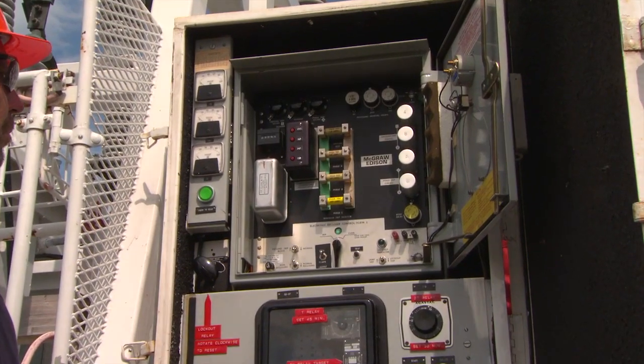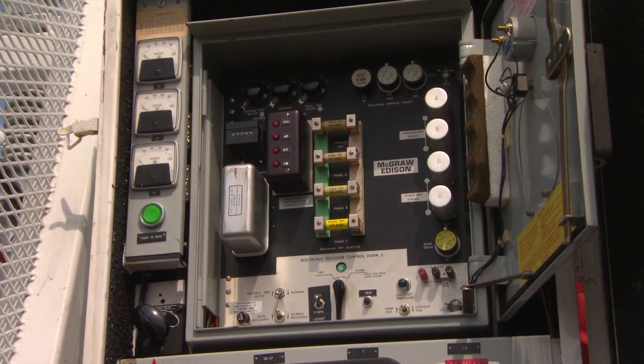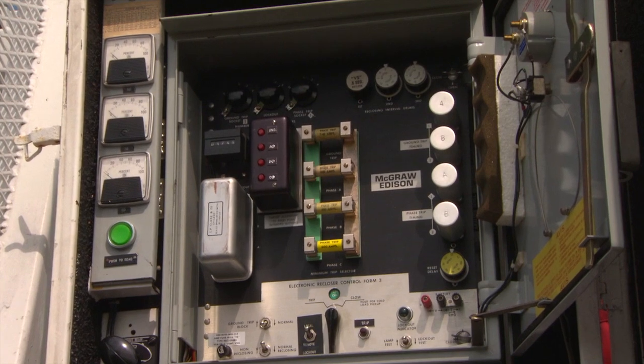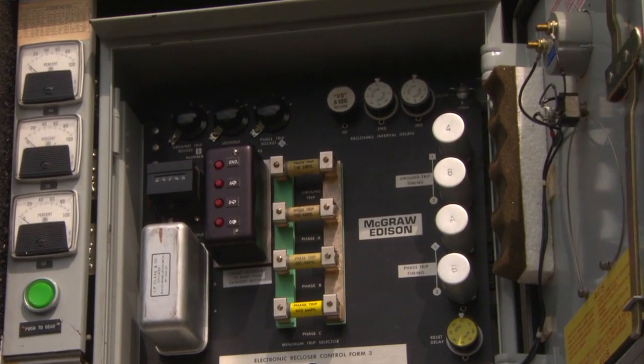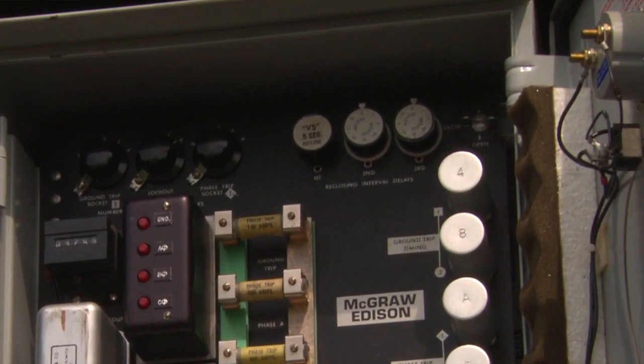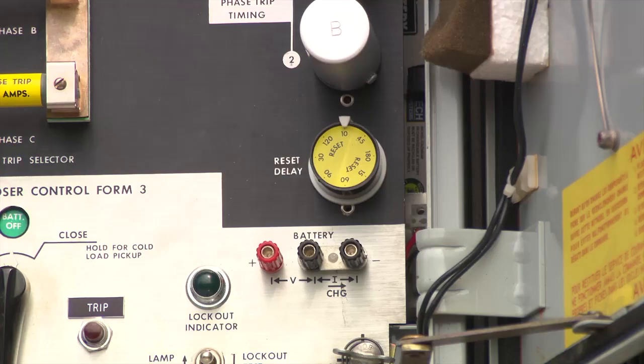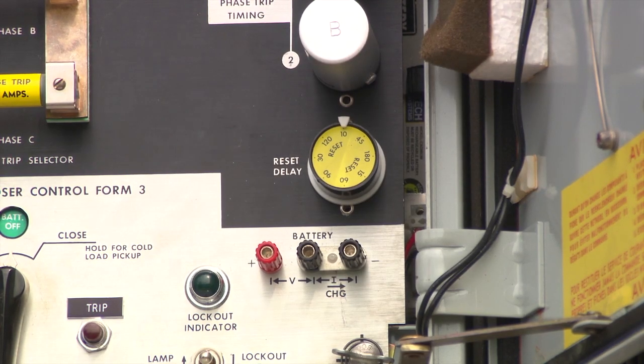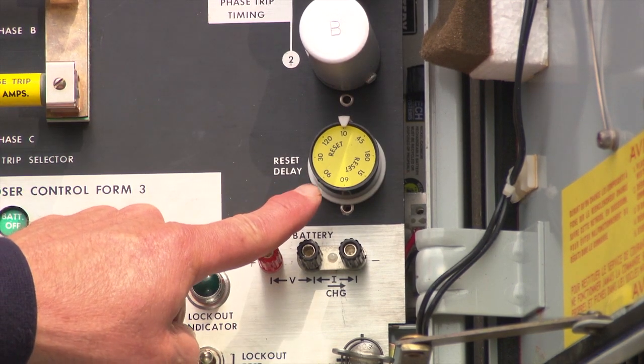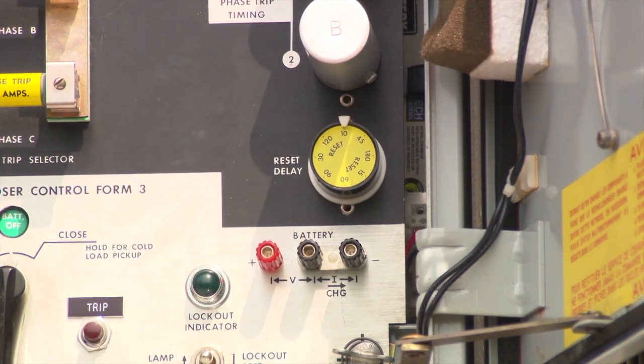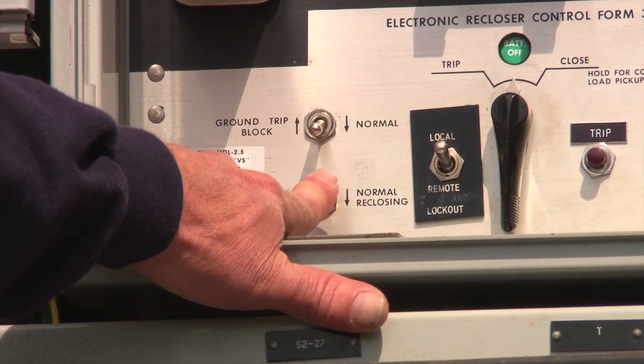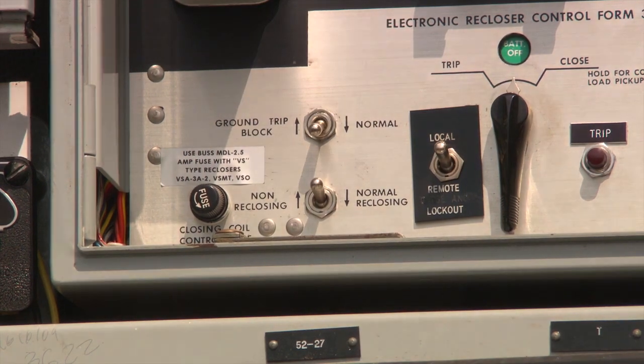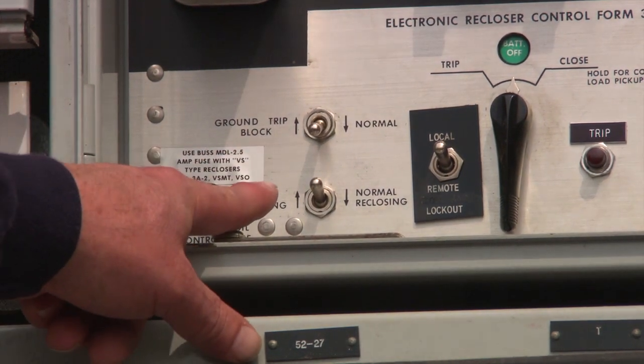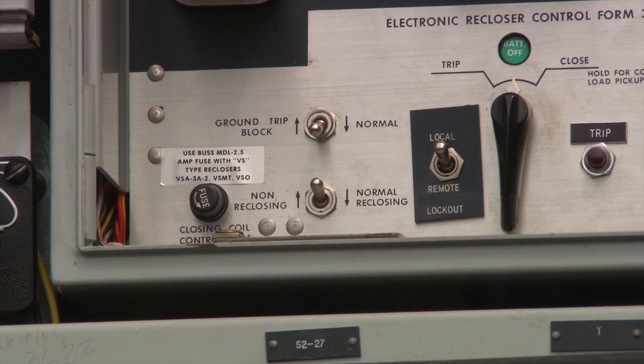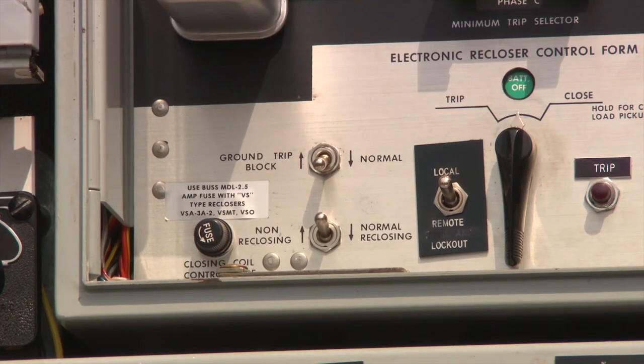The reclosing interval delay should be set as follows. First, to 0.5 seconds. Second, to 2.0 seconds. And third, to 2.0 seconds. The reset delay plug should be set to 10 seconds. This is a solid-state component easily changed to any of the 8 delay values. The non-reclosing normal reclosing switch should be on non-reclosing. This sets the control for a one-shot lockout without disturbing the lockout setting of the operation selector.